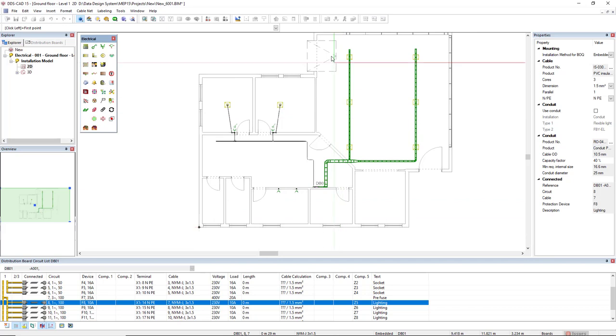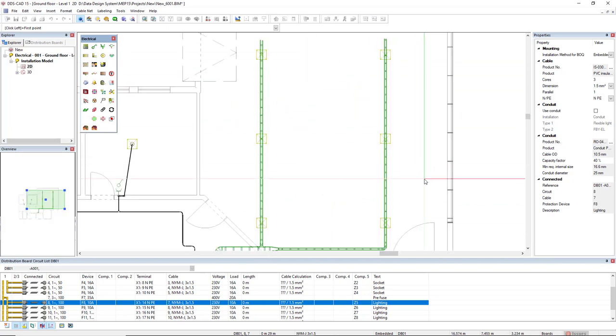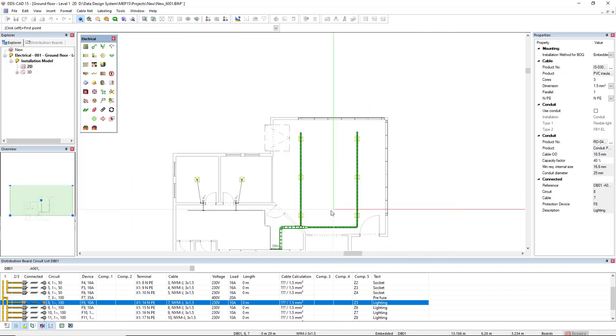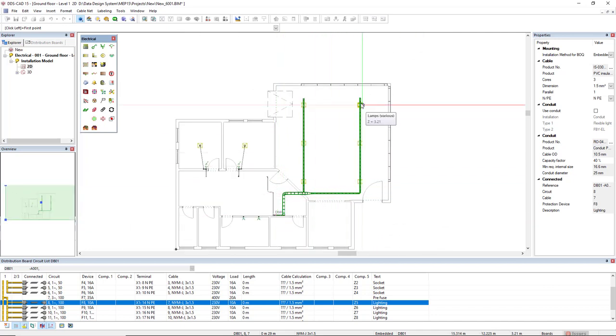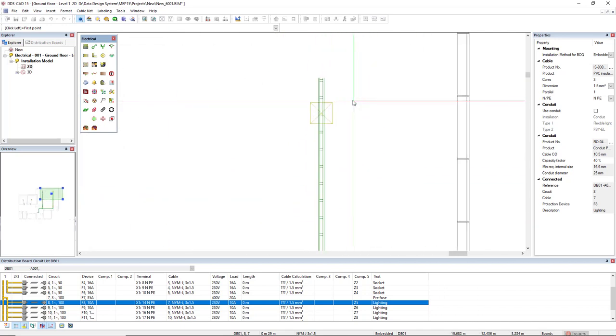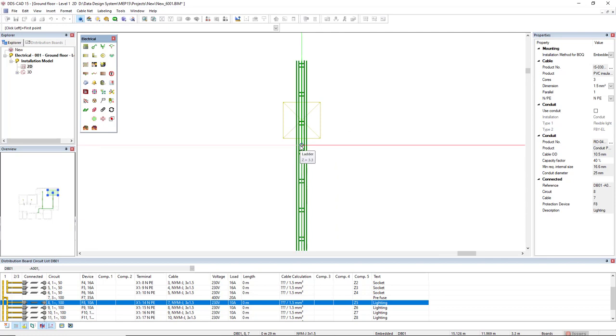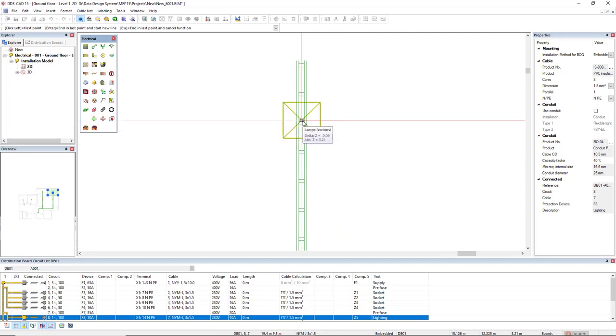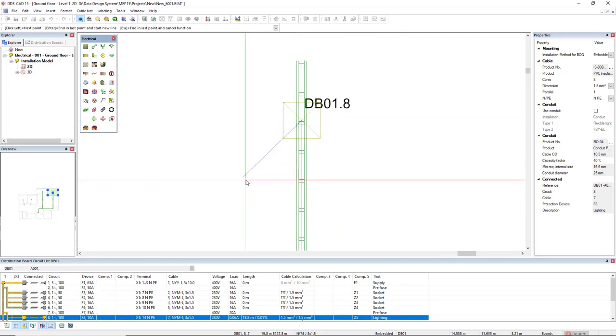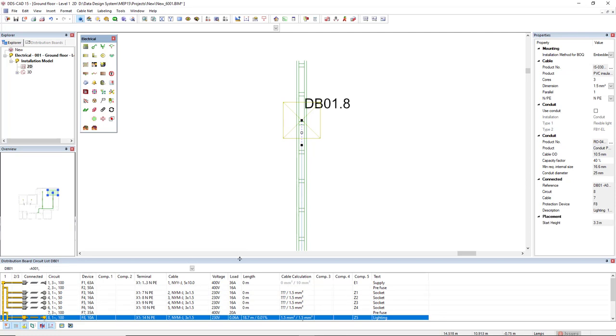And if we go to the showroom, we see here six light features. If we see the worst path is this one, so I will only connect from the ladder to this last lamp or light feature in order to have the worst path for the length of the cable, and then for the voltage drop that we directly see in the circuit list.